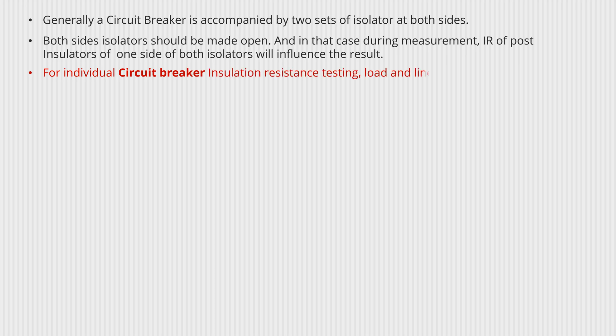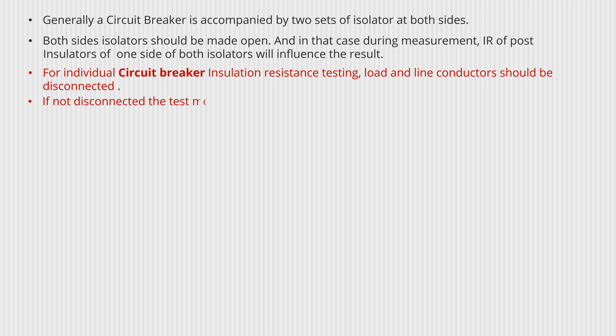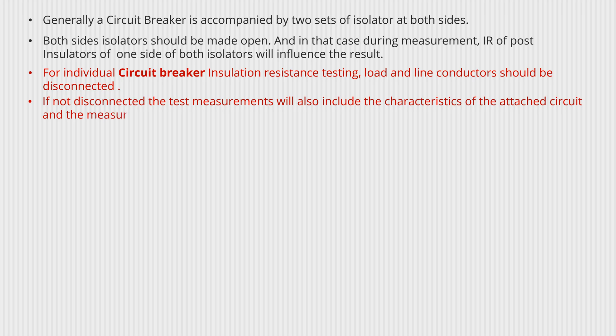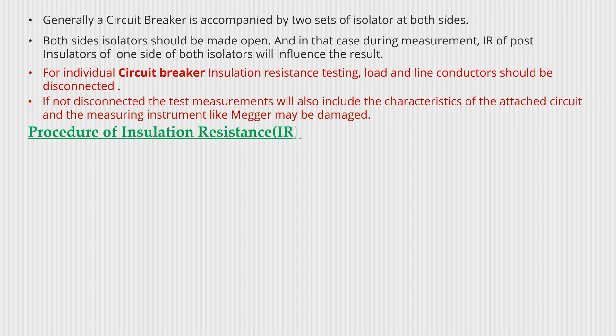Load and line conductors should be disconnected. If not disconnected, the test measurement will also include the characteristics of the attached circuit, and the measuring instrument like the megger may be damaged.